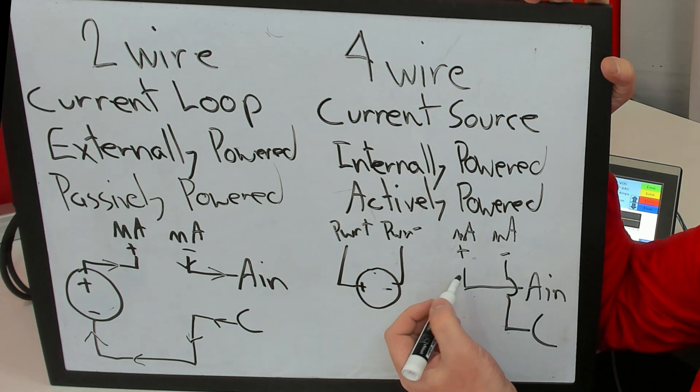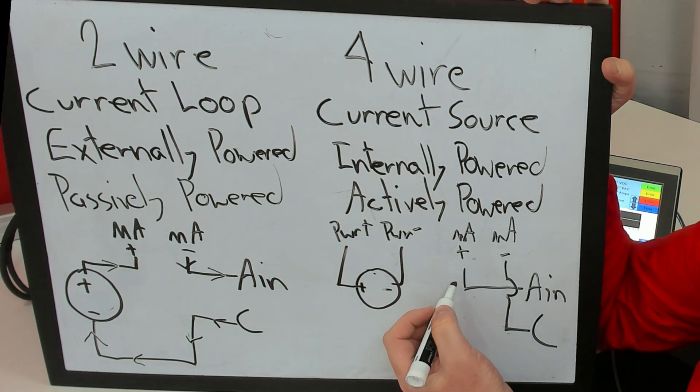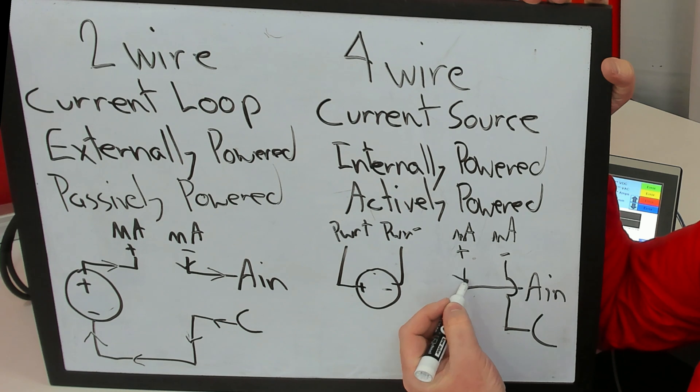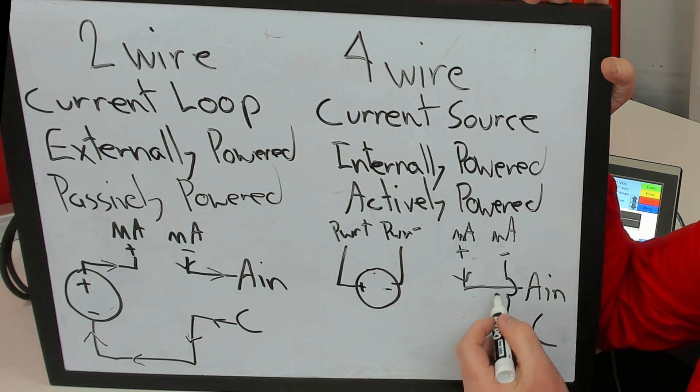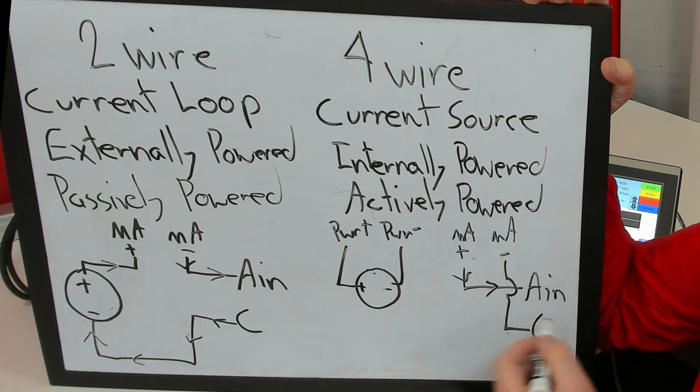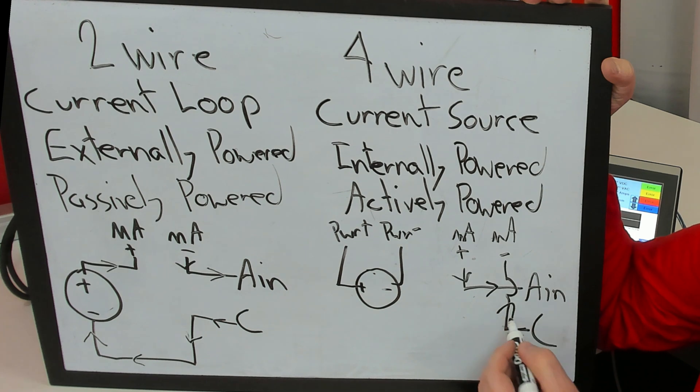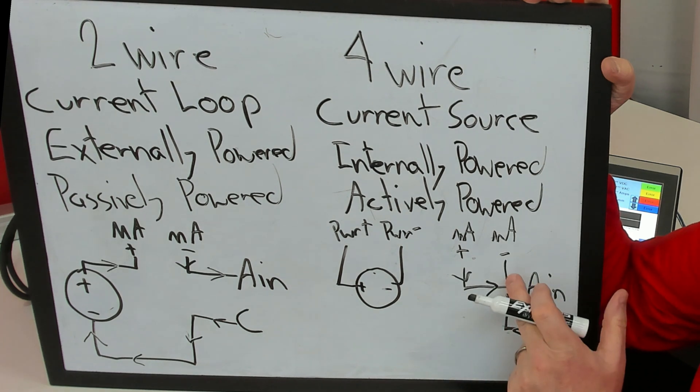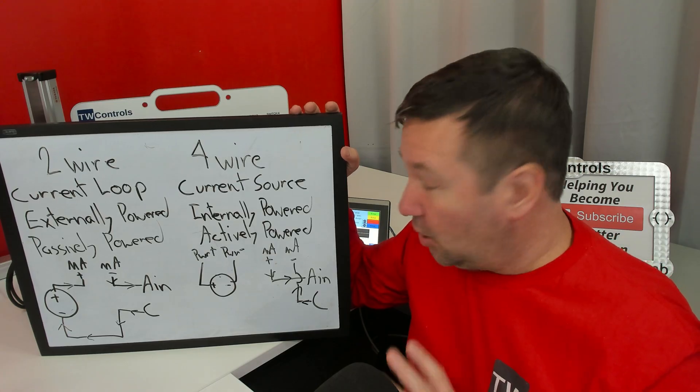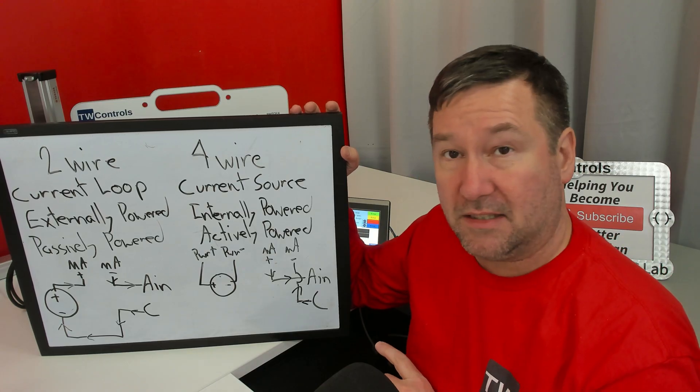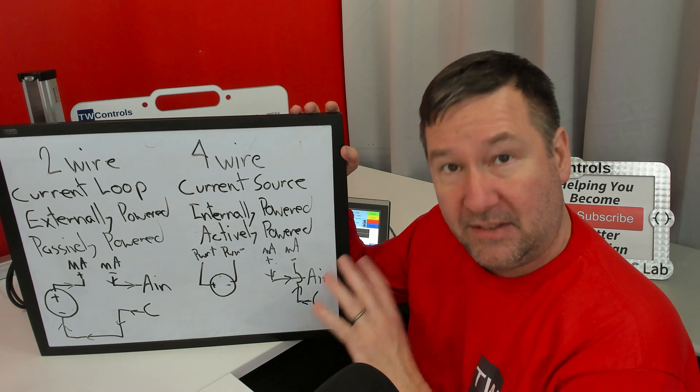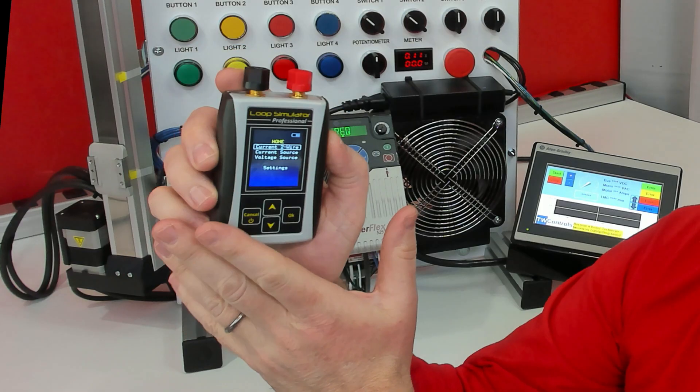In this case, it's generating the entire signal. So it's going to come out of the milliamp plus, into the analog in, out of the common, right back to the power supply. So from a current perspective, we are wired the exact same way.